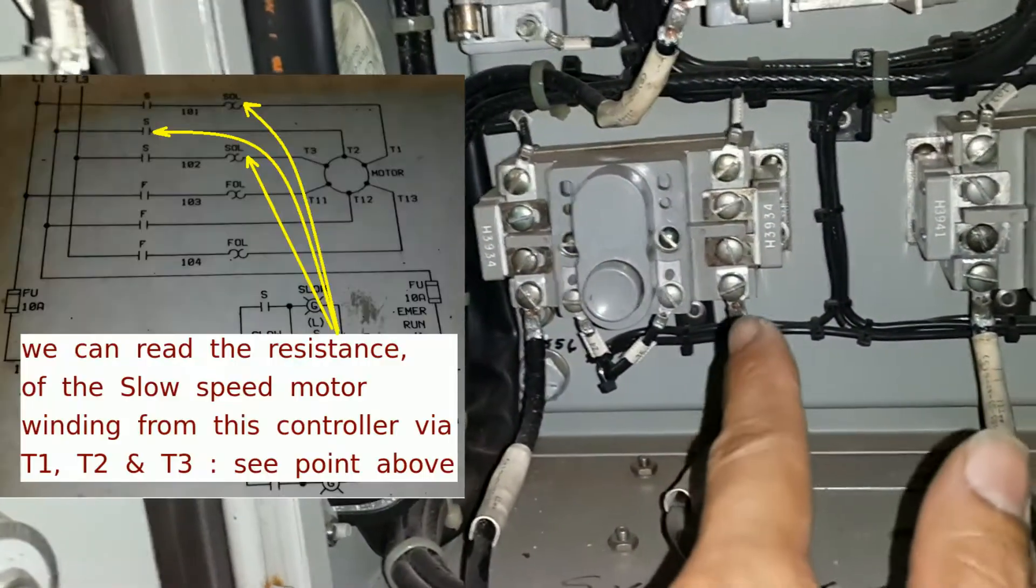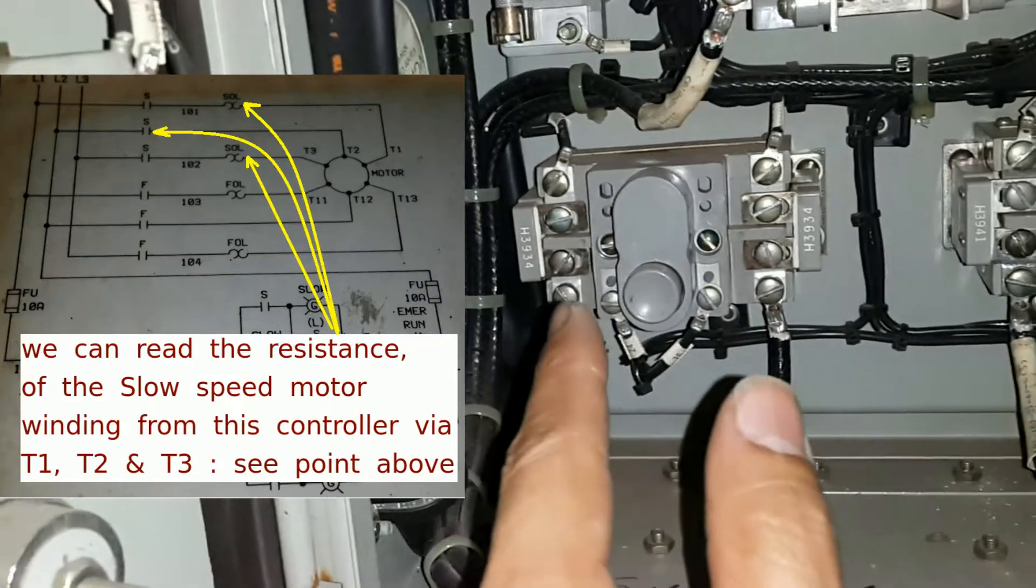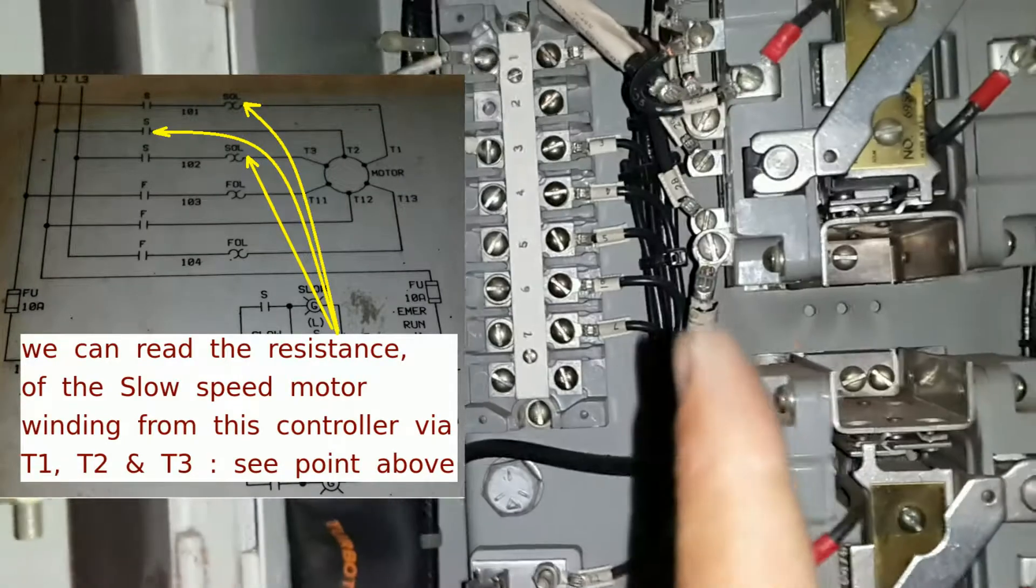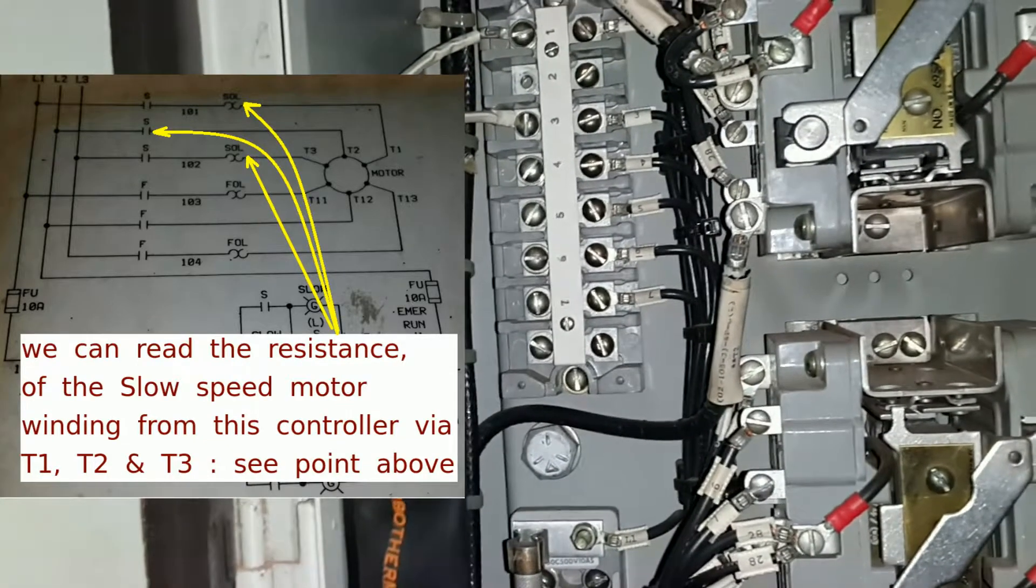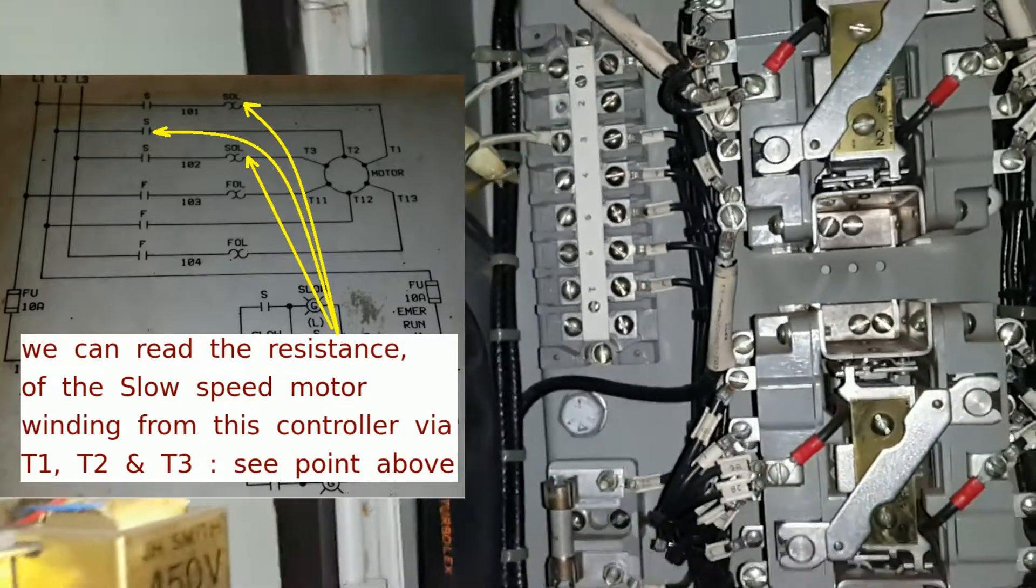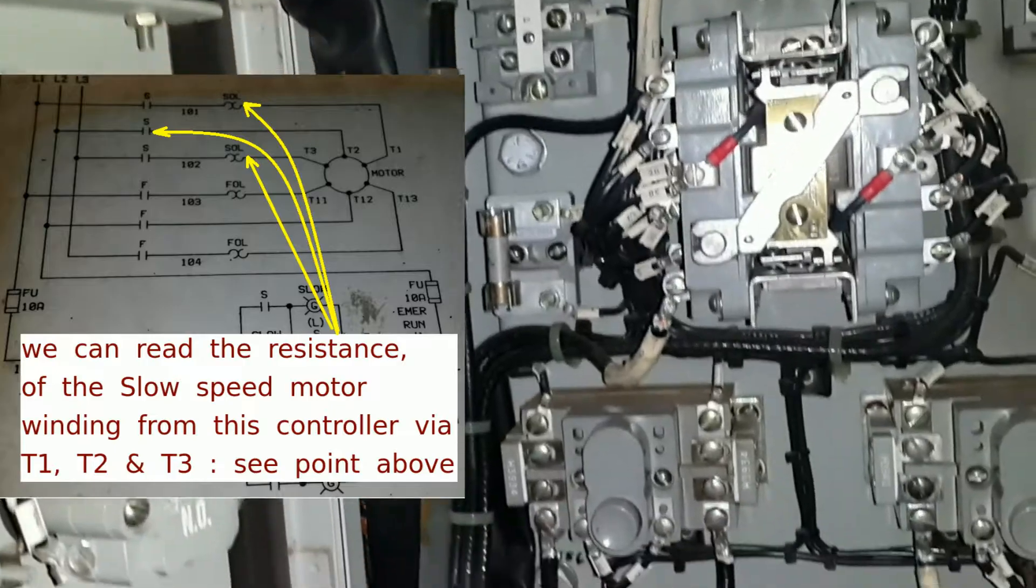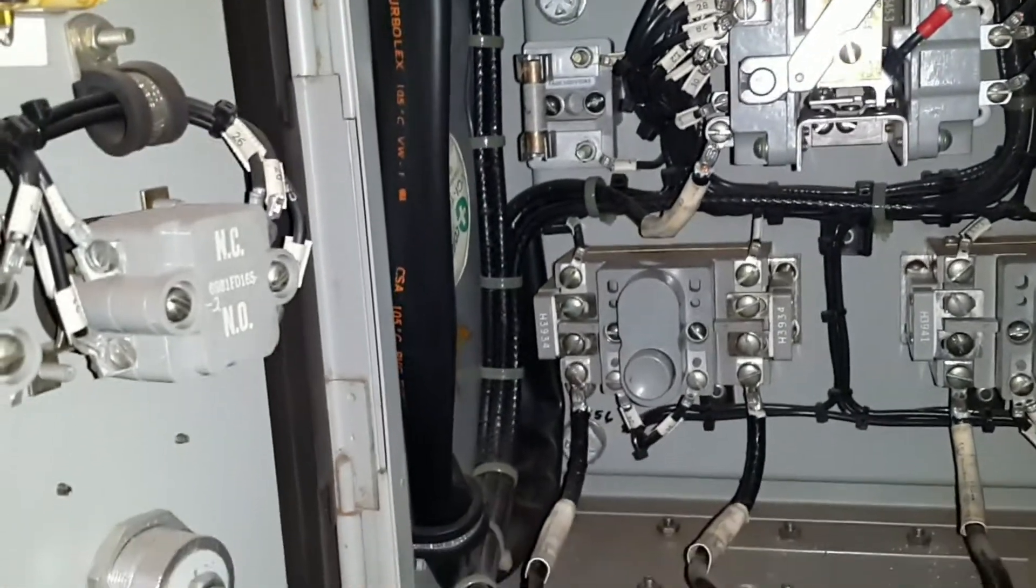If we wanted to read the slow speed windings, then we will have to put a multimeter in there, there, and then there so that we get T1, T2, and T3. And remember, we're always looking for that five percent balance in the motor windings.